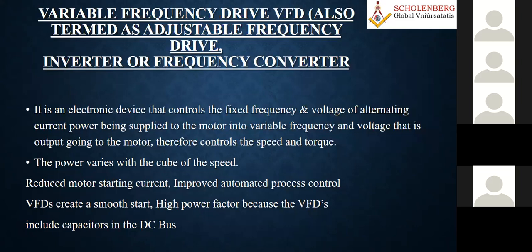So finally, we always go for VFDs now, variable frequency drives, because most of the time we use this type of fans and all the things in partial load condition. VFDs are definitely another latest advanced technology which really helps us to go for energy saving. So you should always ensure that these VFD motors are involved in your design. That is a must actually.